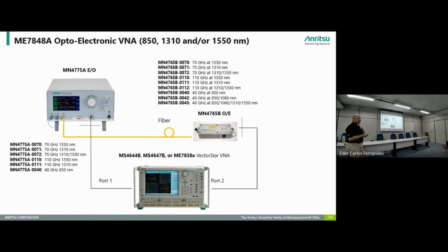So I strongly recommend for the EO and OE measurements to at least have the OE module, because that's the reference. If you need the EO converter, we have that too. But I have plenty of people that will have their own modulator that they'll use here. But modulators drift much more than an OE will. So it's very important to have that OE be rock solid and accurate in terms of its characterization. So then you can use it to characterize a modulator that may be drifting a little bit. This one doesn't because it's got the bias controller built in. But a discrete modulator left on the bench can drift. Generally what drifts on a modulator is the absolute level, not the shape of the response. The absolute level will go up and down, but the shape generally stays the same. But it's still annoying to have that level going up and down.